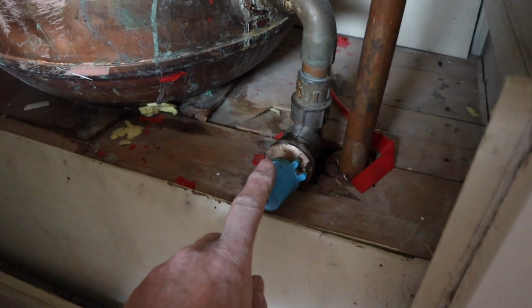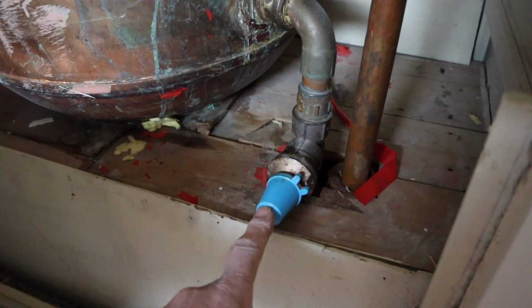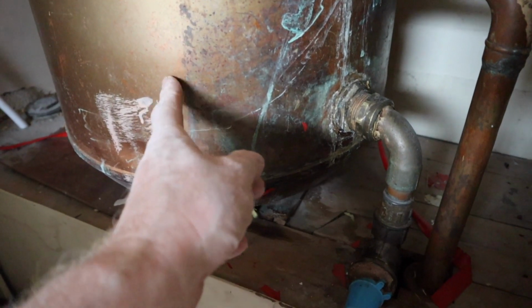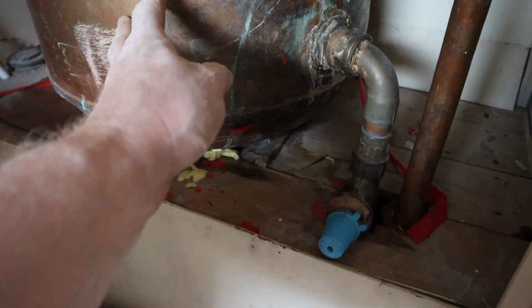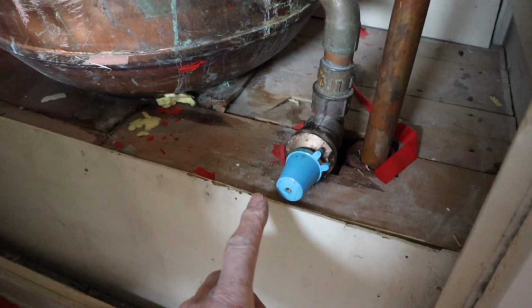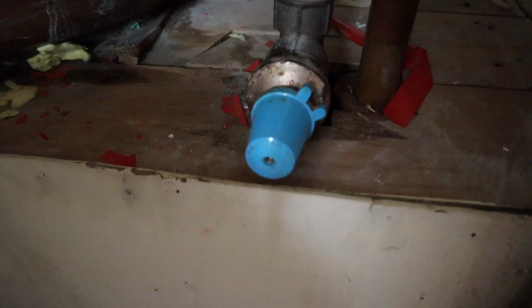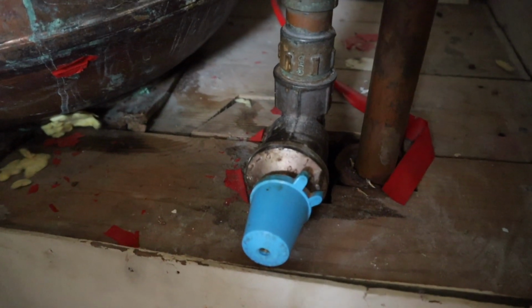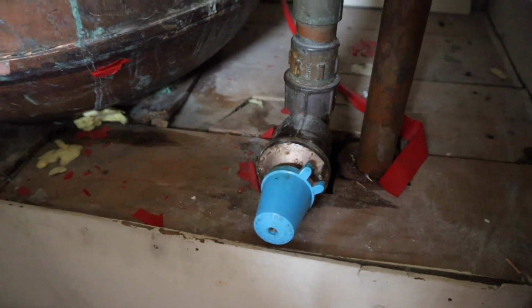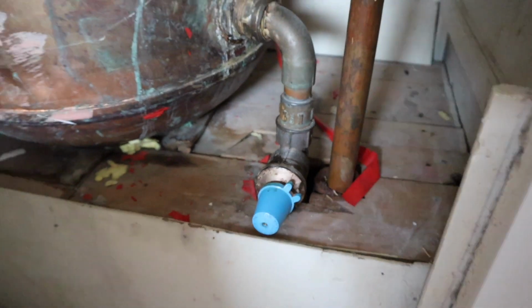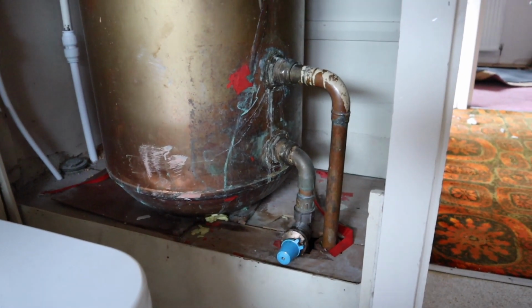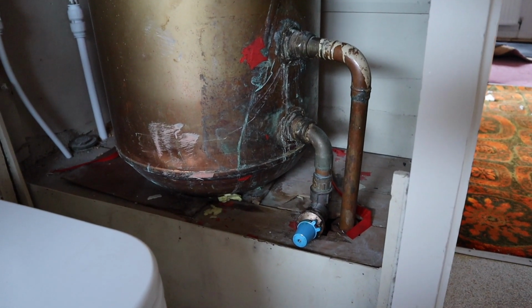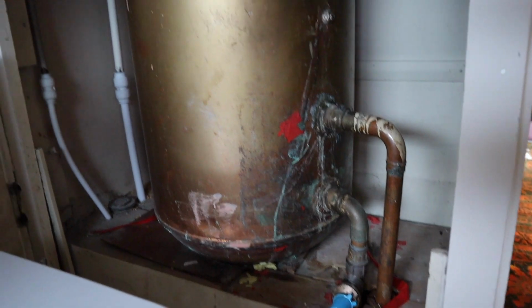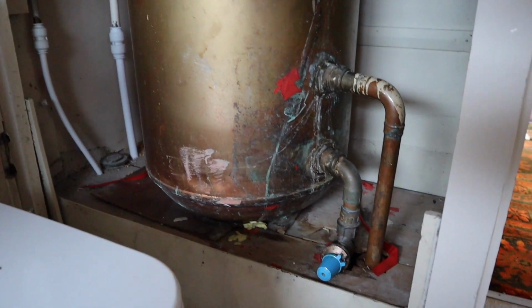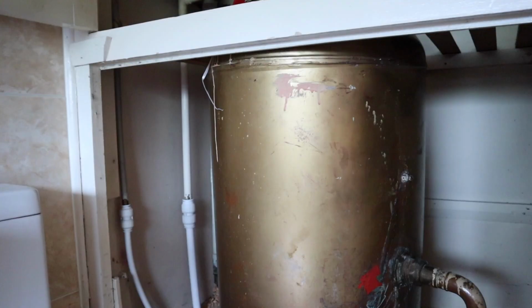They actually improved this by putting a stat on the cylinder, so it will be temperature controlled via a stat on the cylinder, which you can still get now. But that's a very old Drayton controller. Well, if memory serves, it's a Drayton controller. And that controls the temperature, or tries to control the temperature of the cylinder to make sure it doesn't go over 65 degrees.